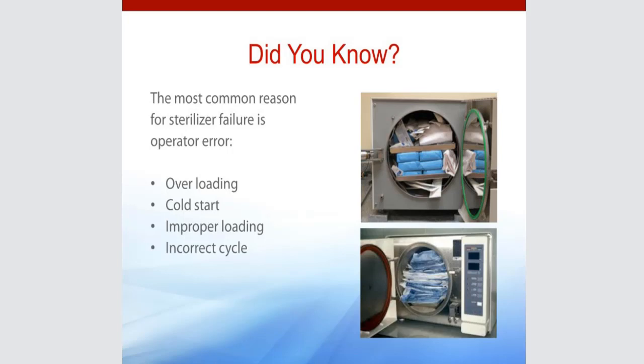When we talk about BI failures, the number one reason is demonstrated in both of those sterilizers. Overloading a sterilizer, you're going to have a failed BI for certain. That's the number one reason that spore tests failed. Either you've overloaded or you've not loaded appropriately. So user error comes into play. And you need to make sure that you're doing your decision tree when you have a failure. What could have been the things that possibly have gone wrong? Correct that and then do the retest. If the retest passes, you can go ahead and use the sterilizer again. If not, you've got that third time's a charm technique to do.